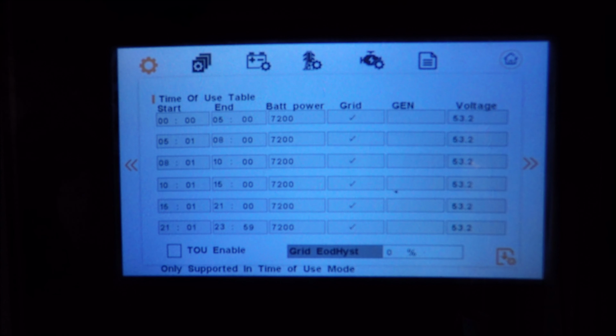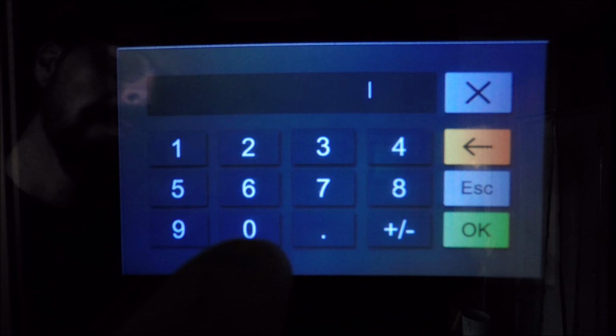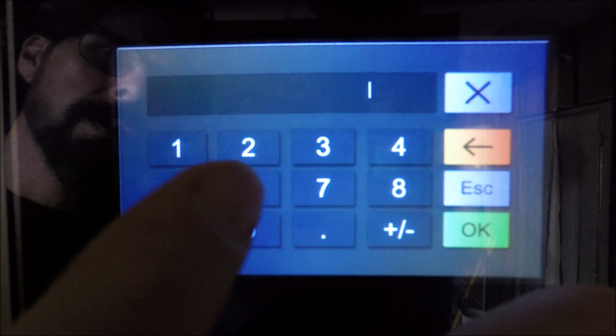Now, what I want is during my peak usage time, which is between 4 p.m. and 9 p.m. in most areas in the United States, we are going to allow the use of our batteries during that 4-hour time slot. What we're going to do is go to our 4th time slot, and we're going to change the 15. Remember, we're in 24-hour time here, so we're going to change this 15 to 16.